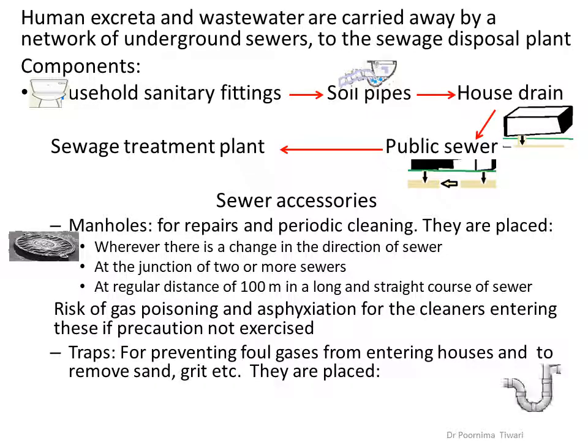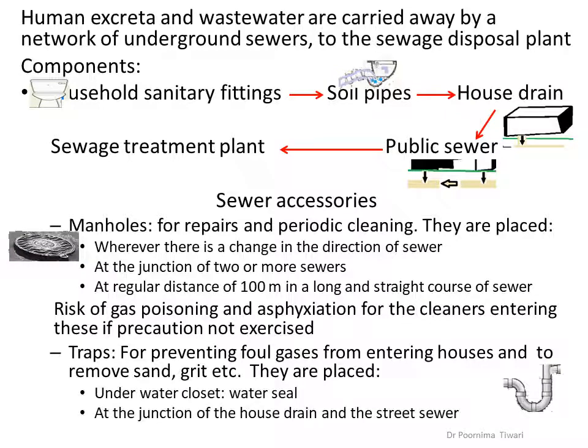Another sewer accessory is traps. The purpose of traps is to prevent foul gases from entering houses or streets and to retain sand, grit, etc. from sewage. Traps are placed at the water closet in household fittings, at the junction of the house drain and street sewer, and where surface water enters the sewers if storm water is also carried by sewers.